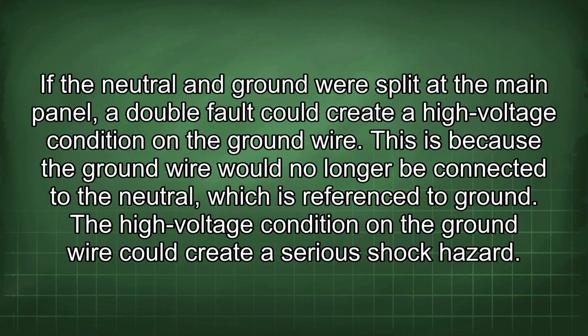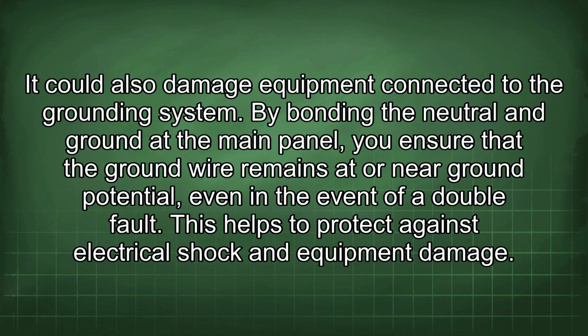on the ground wire. This is because the ground wire would no longer be connected to the neutral, which is referenced ground. The high voltage condition on the ground wire could create a serious shock hazard. It could also damage equipment connected to the grounding system. By bonding the neutral and ground at the main panel, you ensure that the ground wire remains at or near ground potential, even in the event of a double fault. This helps to protect against electrical shock and equipment damage.